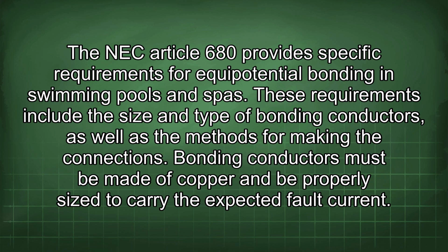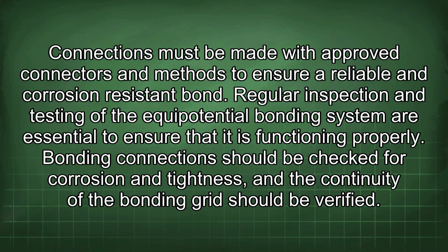The NEC Article 680 provides specific requirements for equipotential bonding in swimming pools and spas. These requirements include the size and type of bonding conductors, as well as the methods for making the connections. Bonding conductors must be made of copper and be properly sized to carry the expected fault current. Connections must be made with approved connectors and methods to ensure a reliable and corrosion-resistant bond.